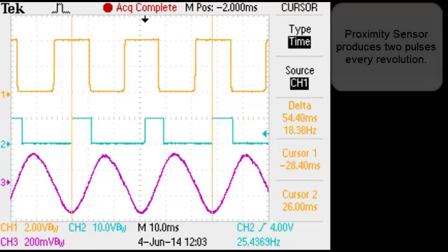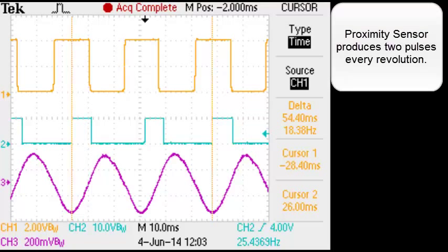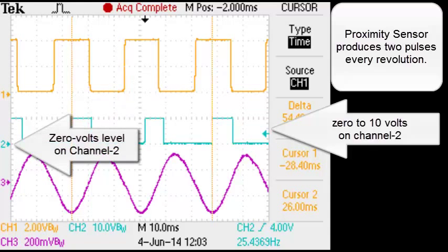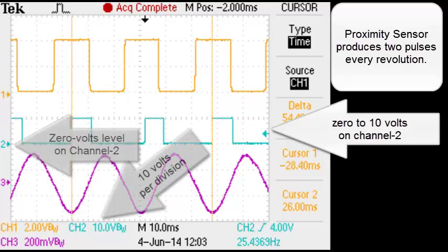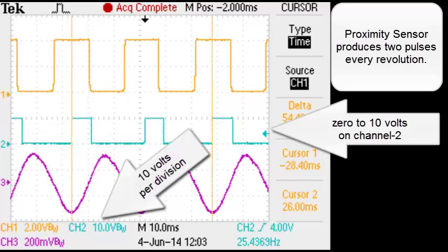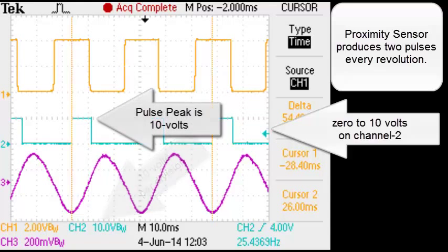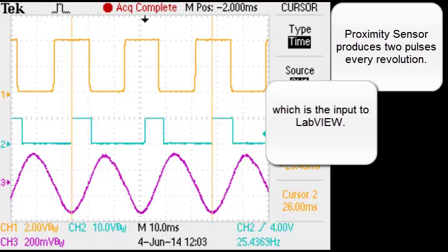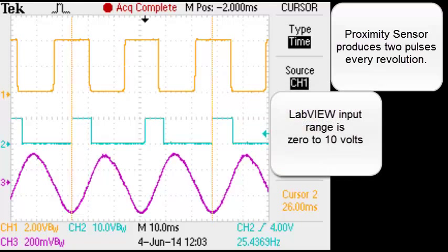The oscilloscope can also measure speed. The proximity sensor produces two pulses every revolution. We go from 0 to 10 volts on channel 2. That's the 0 volts level on channel 2, set at 10 volts per division. Therefore, the pulse peak is 10 volts, which is the input to LabVIEW. LabVIEW input range is 0 to 10 volts.